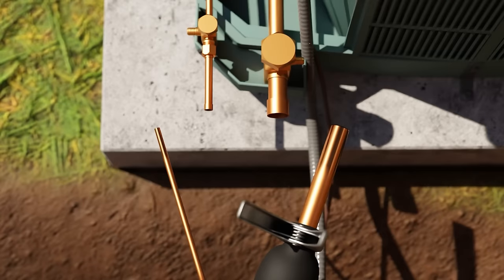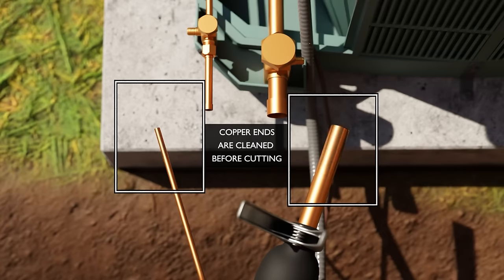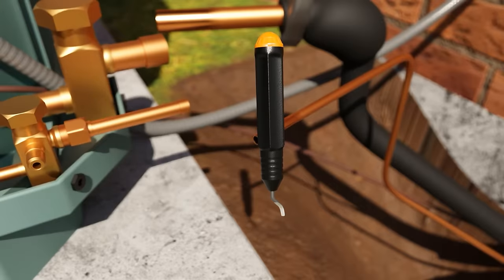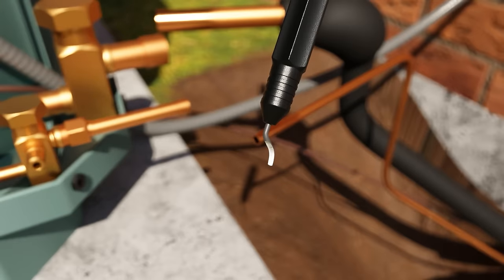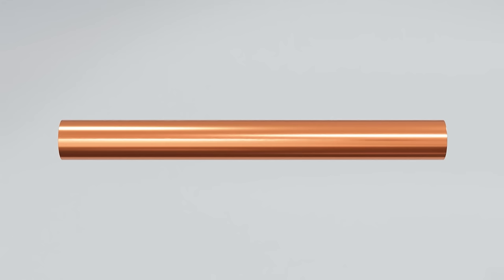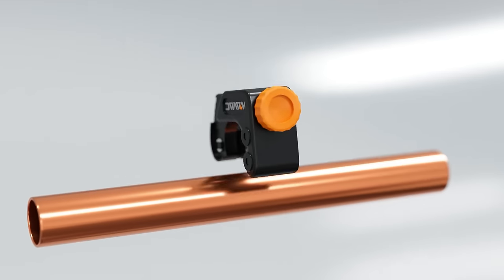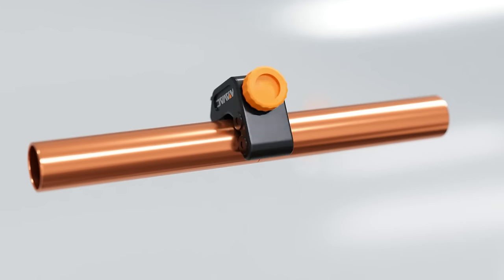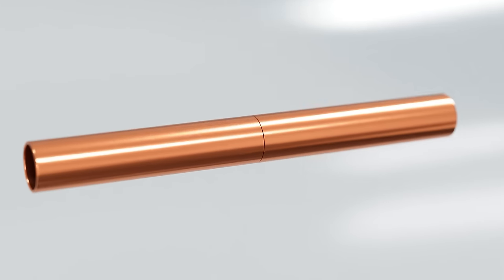Before cutting copper in the first place, be sure to clean it with an emery cloth or other abrasive pad. Ream or deburr the copper tubing. Here we're showing how to do that using a NAVAC deburring tool. You can see that when you cut copper it pushes a burr into the inside of the tubing.